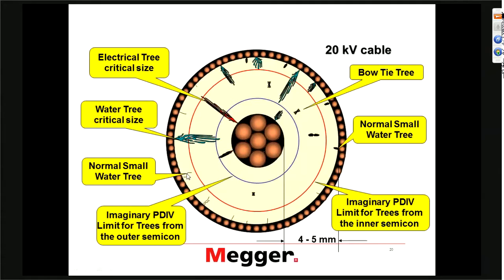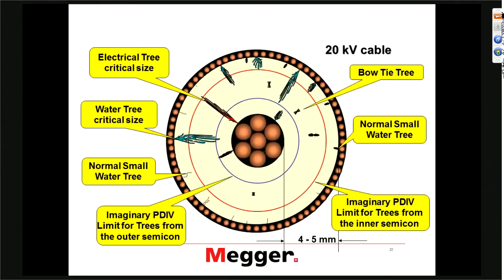A water tree of critical size has already crossed about three-quarters of the insulation. These are the types of water trees that, when you do the VLF test, will get converted to electrical tree and now grow very rapidly to failure. With small water trees, the high voltage test level of the VLF test will not do anything — they just sit there, because the electrical field is much smaller at their tip. That's really the combination of the electrical field created by the water tree itself and the superimposed electrical field from the test voltage that makes the conversion.